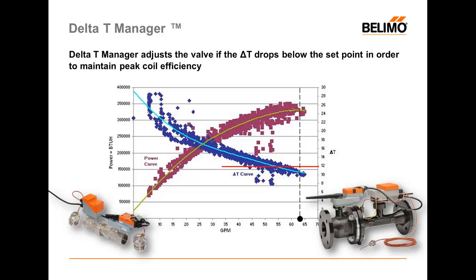Let's take an example here. Suppose the valve is flowing 64 gallons a minute. At this rate, we're achieving a very high amount of BTUs relative to the performance of the coil, but we're also creating a low Delta-T when we do that. We can see at this point the Delta-T is just above 10 degrees Fahrenheit, and we're creating about 325,000 BTUs.